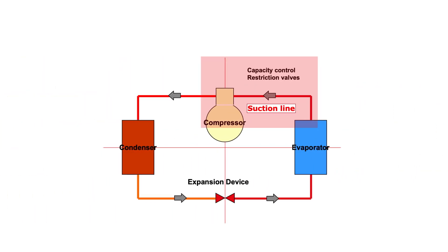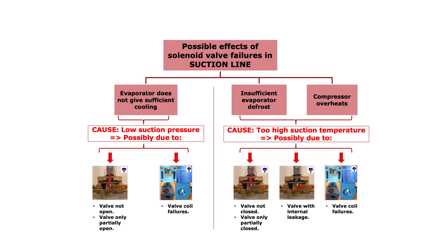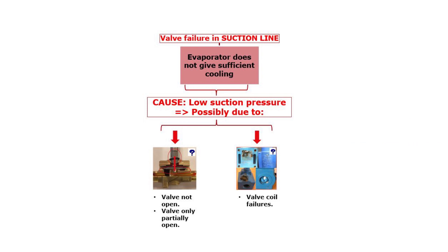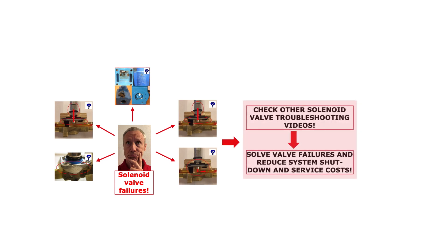Looking at the suction line as illustrated here, you normally use solenoid valves for capacity control and restriction. Here you see an overview of how possible solenoid valve failures might affect the refrigeration system when the valve is located in the suction line. The evaporator does not give sufficient cooling — caused by too low suction pressure due to the valve not opening or only being partially open, or the valve coil is not working correctly. Insufficient evaporator defrost and or compressor overheats — caused by too high suction temperature due to the valve not closing or only being partially closed, the valve is internally leaking, or the valve coil is not working correctly. Check out the other online solenoid valve troubleshooting videos to get more details and how to solve them to efficiently reduce system shutdown and service costs.